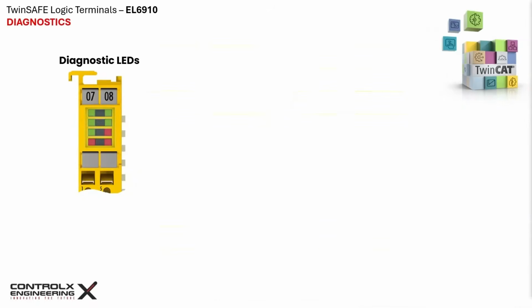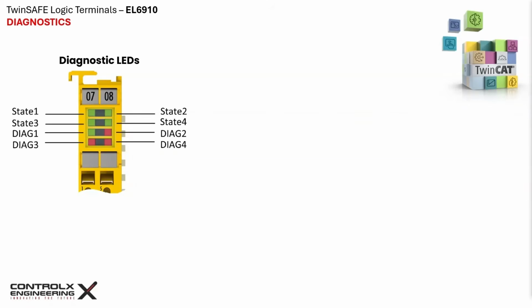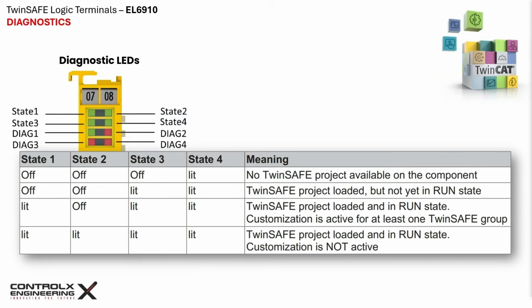Like every other Beckhoff terminal, the EL6910 also has LEDs, which provide valuable diagnostic information about the state of the terminal. The top two rows have 4 green LEDs for status indication, and the LEDs in the bottom 2 rows indicate diagnostic information. This table shows the meaning of the various state LEDs. A brand new EL6910 out of the box without a project will only have the state 4 green LED lit. Once a safety project is loaded and in run mode, all 4 LEDs are illuminated.